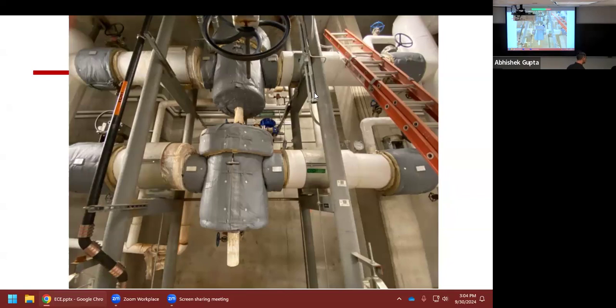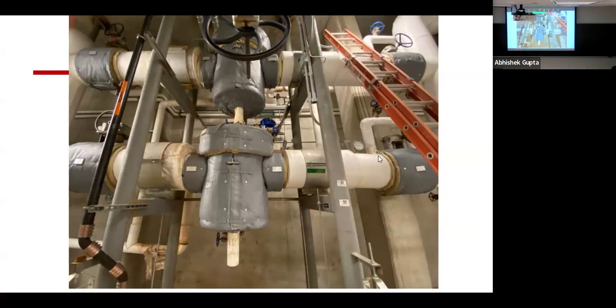This is an example of a de-superheater. These are giant valves that have high-pressure steam going through them. It's definitely scary when we turn these systems on because the water immediately flashes into steam and you hear lots of banging sounds. We have electronic control systems that control this, and if you watch the experienced people, they're usually at the door when turning on these systems so they can leave if there's some sort of malfunction.